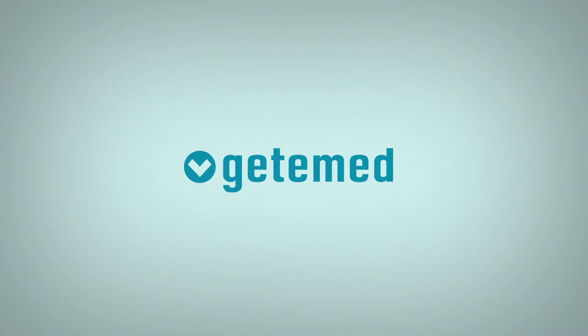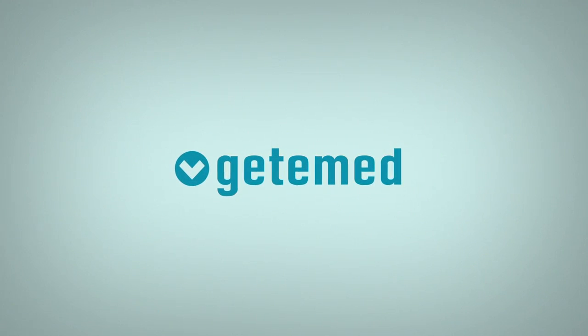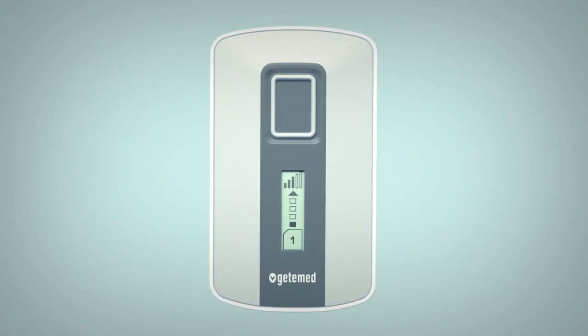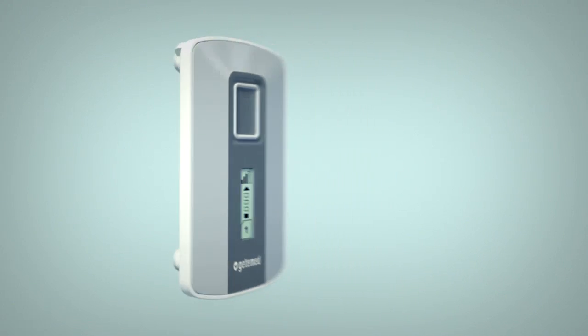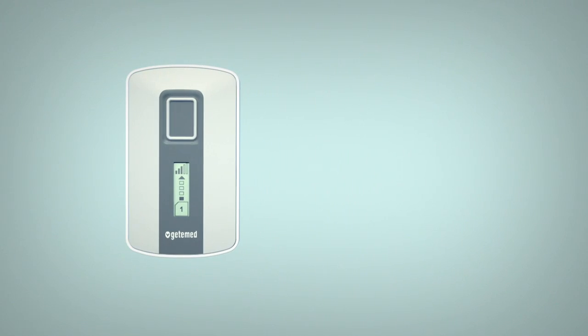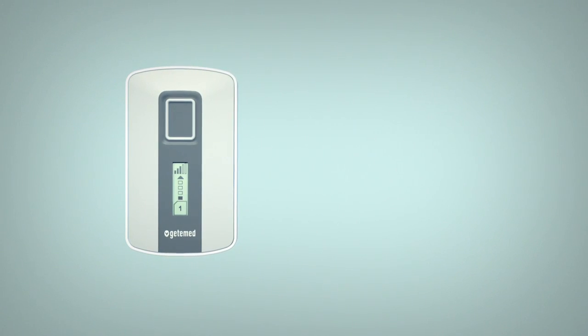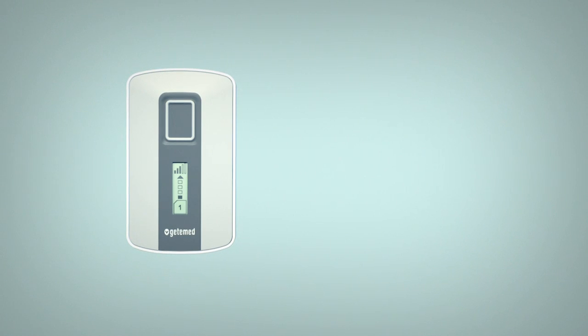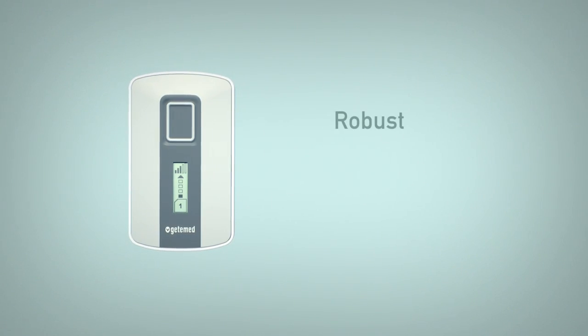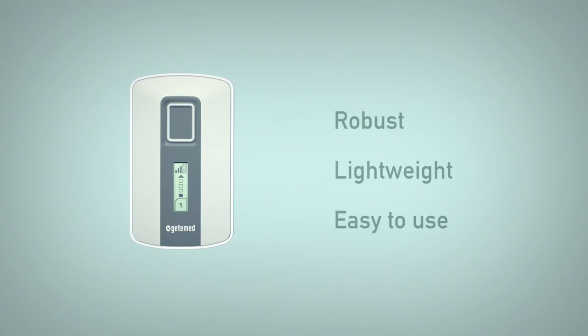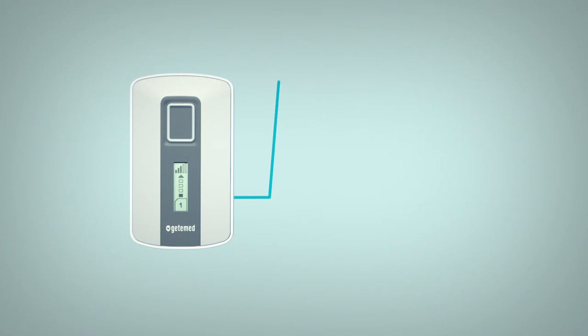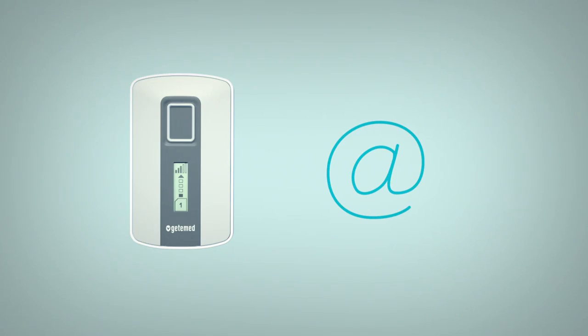To overcome this challenge, a quite simple method has come into play more and more over the past couple of years, the so-called tele-ECG. GETEMED AG's latest development in this area is the PhysioMem PM100. The PhysioMem PM100 is a robust, lightweight and easy-to-use device which enables the patient to acquire a 2-lead 40-second ECG strip at any time in any place. Upon completion, the device automatically transmits the recorded ECG to the attending physician via email.